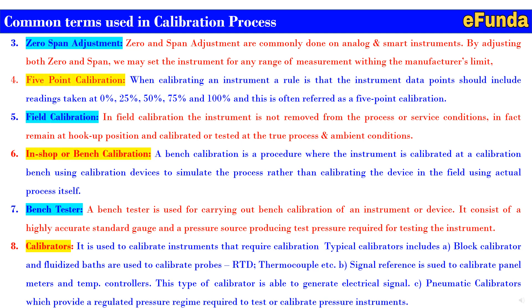Eighth is the calibrator, used to calibrate instruments requiring calibration. Calibration stations typically include: (A) a block calibrator and fluidized bath, used to calibrate probes, RTDs, and thermocouples; (B) a signal reference used to calibrate panel meters and temperature controllers — this type generates electrical signals; and (C) a pneumatic calibrator, which provides a regulated pressure regime required to test or calibrate pressure measuring instruments.